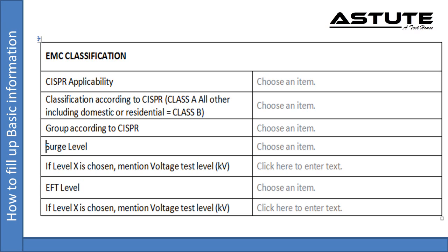Level 3. Typical industrial environment. The installation is characterized by the following attributes. No suppression of EFTB in the power supply and control circuits which are switched only by relays, no contactors. Poor separation of the industrial circuits from other circuits associated with environments of higher severity levels. Dedicated cables for power supply, control, signal, and communication lines.